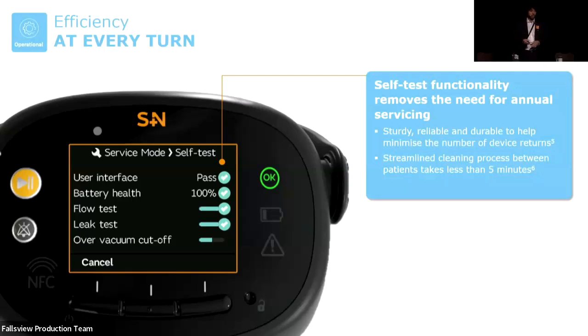So you clean it, you restore the default setting, so you delete the patient data, and it's ready to go. So the whole process takes less than 5 minutes. And this is why we said the pump doesn't need any preventive maintenance, because you're basically doing a mini maintenance, so to speak, every other patient. So it gives you even the confidence that it's working fine before moving into the next step.